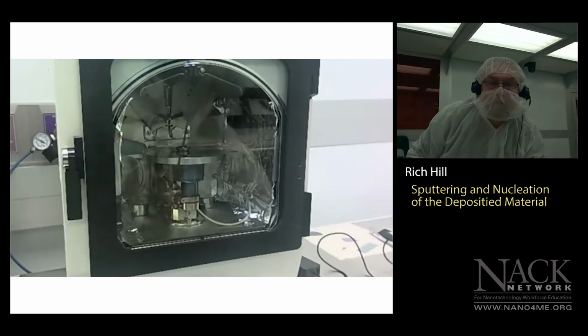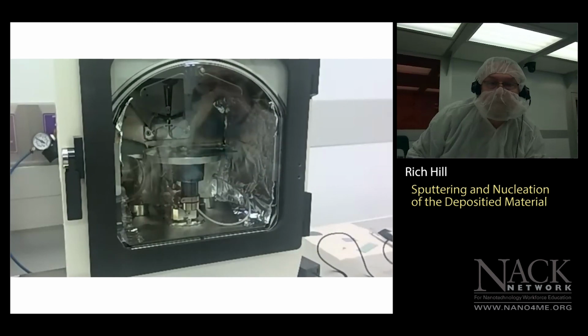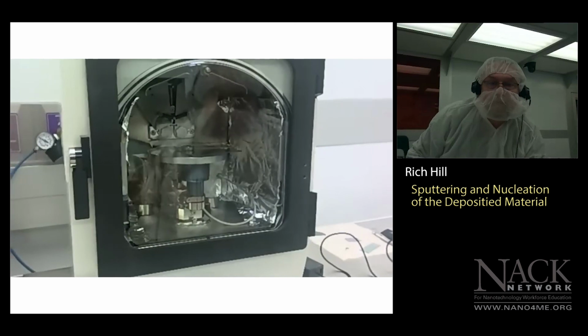So it's just a thread. We thread it on there. It's not a strong thread. It's pretty thin. It's not super thin, but it's not strong. When you thread it into the system to get it ready, it goes around 5 screws in a weaving pattern, like a sawtooth. And then each of those threads fires off so many times to deposit our carbon onto a sample for us.